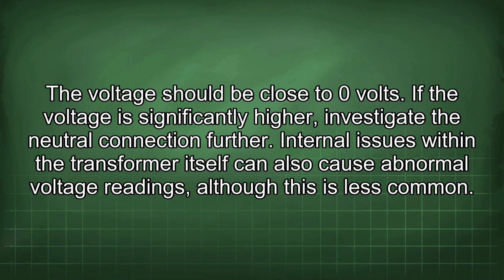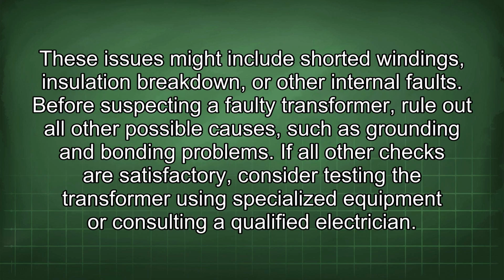Internal issues within the transformer itself can also cause abnormal voltage readings, although this is less common. These issues might include shorted windings, insulation breakdown, or other internal faults. Before suspecting a faulty transformer, rule out all other possible causes, such as grounding and bonding problems. If all other checks are satisfactory, consider testing the transformer using specialized equipment or consulting a qualified electrician.